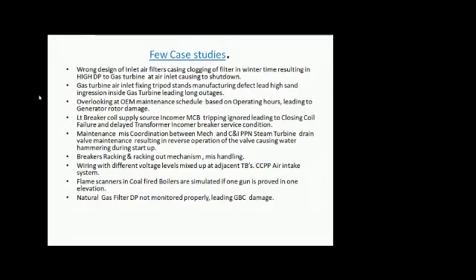And also, in a few gas-based power plants, there are filter DPs. In a power plant where natural gas is the fuel, the DP of the filters was not properly monitored. That has led to damage of the gas compressors.